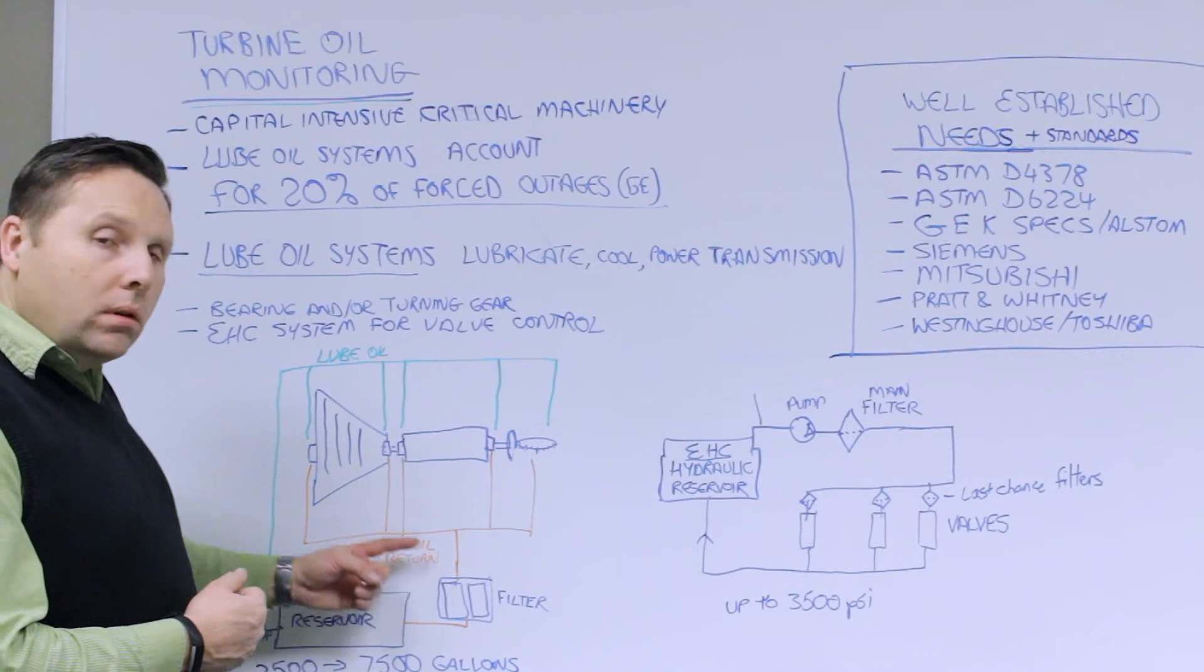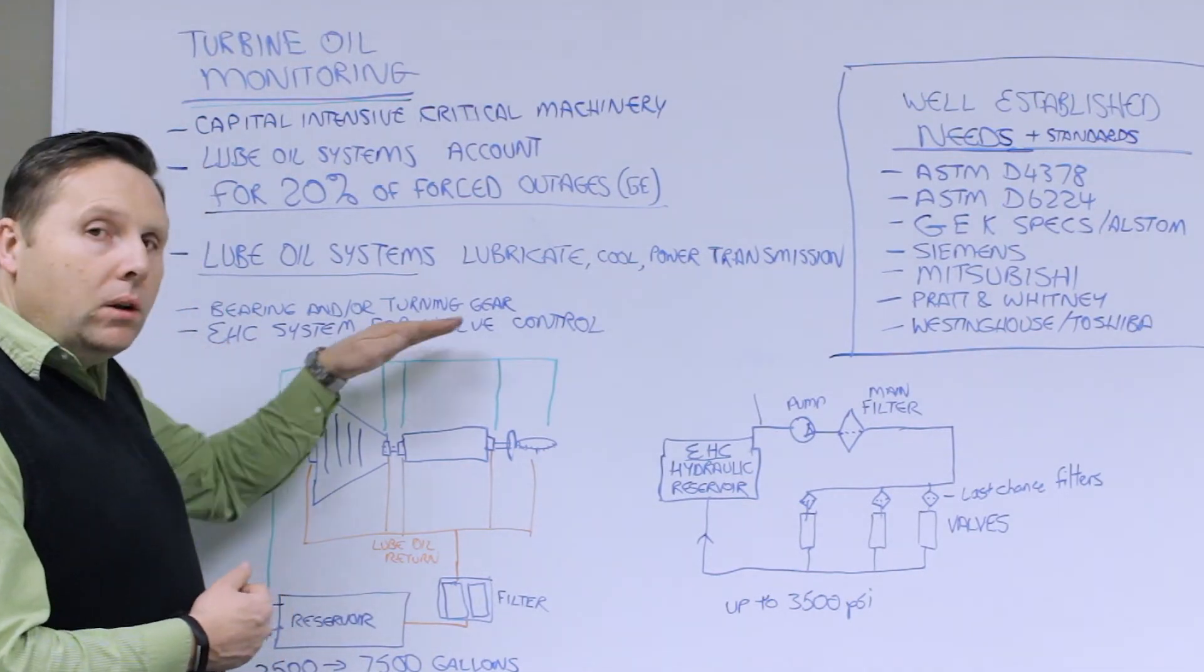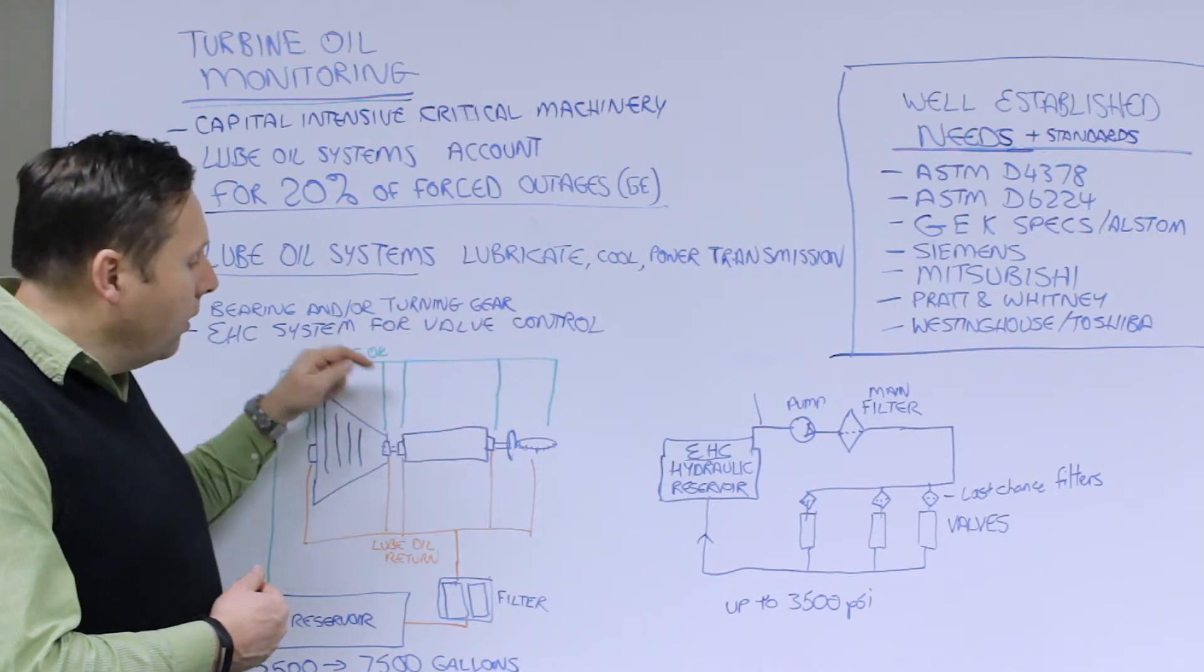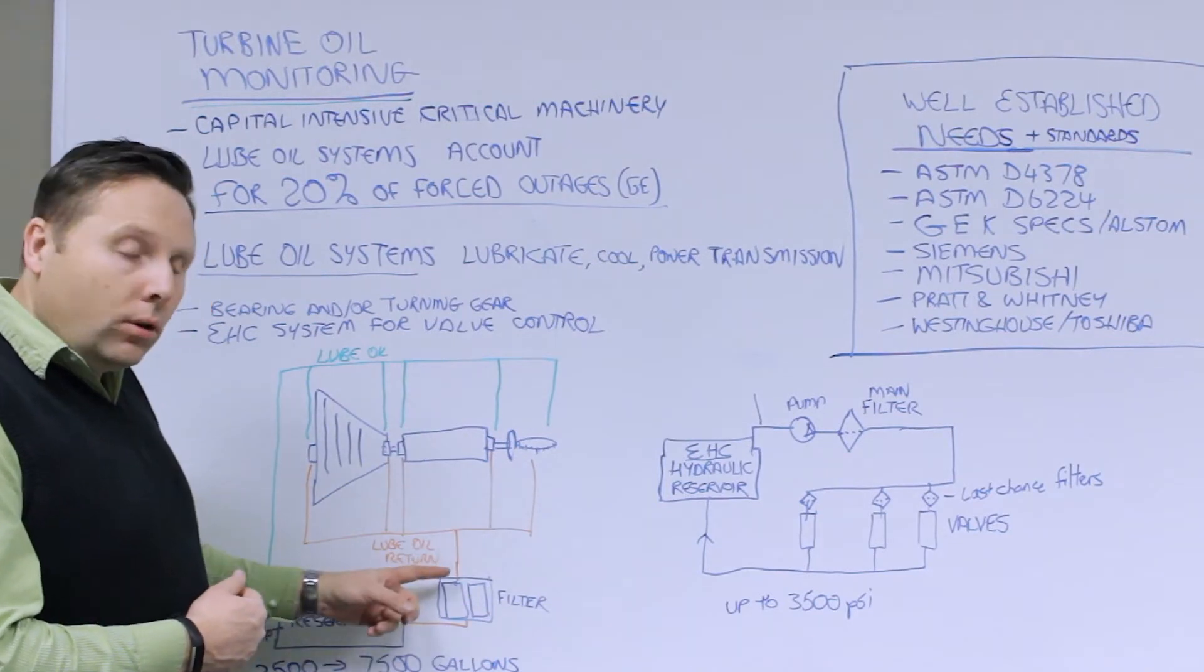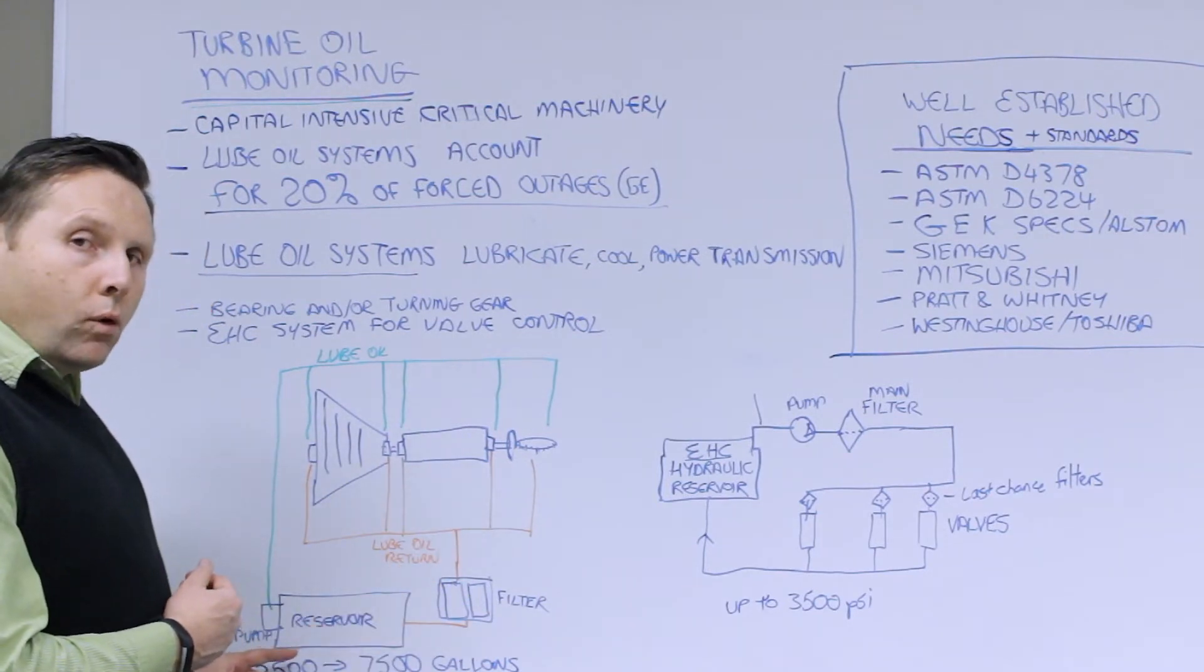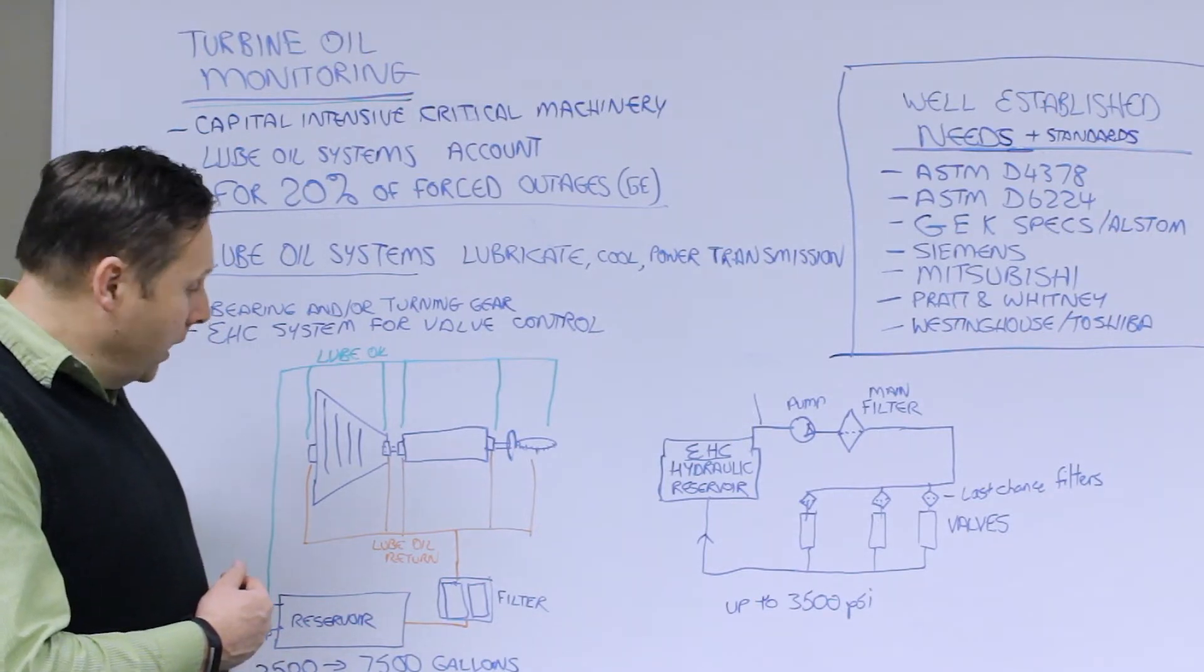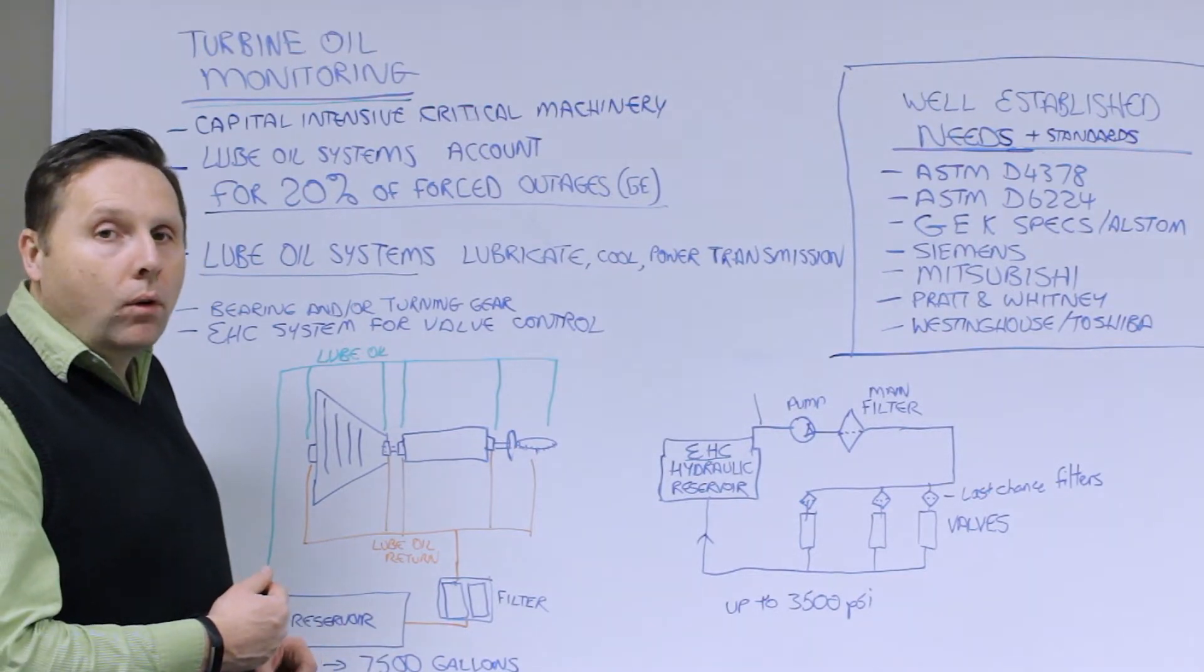And what we have is some sort of centralized lubrication system where we're pumping fresh clean oil up into the system and then gravity fed or pressure fed at a low rate through the bearings and then all comes back, gets filtered back into a large reservoir. These reservoirs are quite large. They can be anywhere from on steam turbine systems from 2,500 to maybe 7,500 gallons of oil.